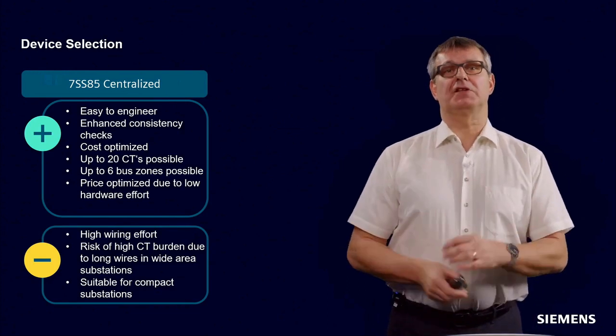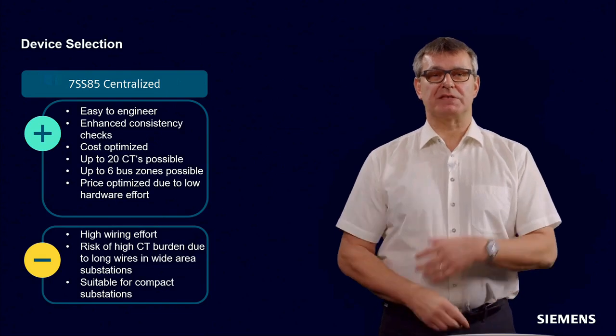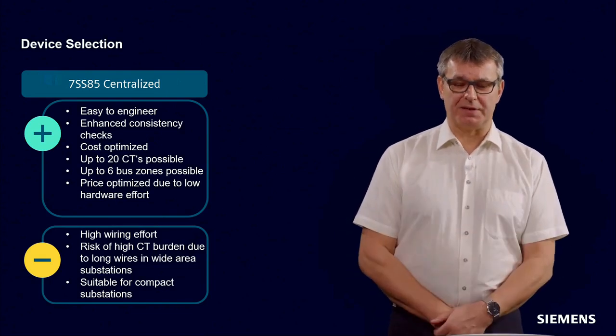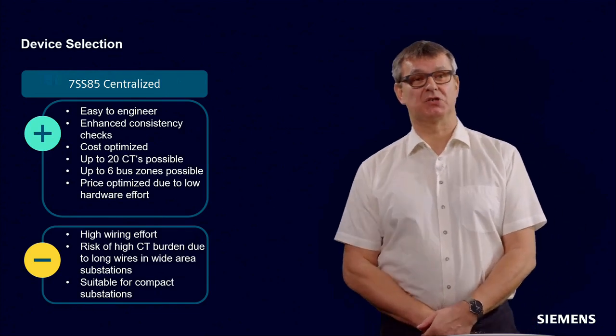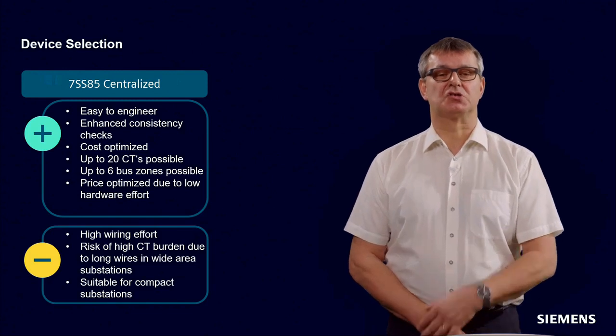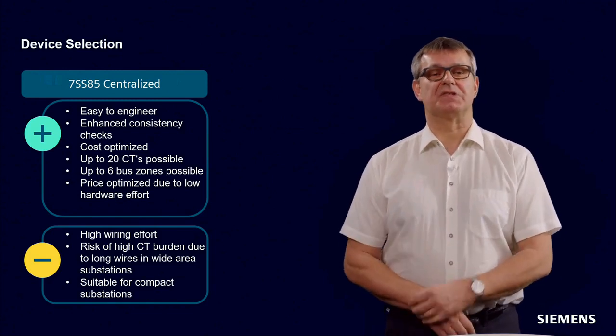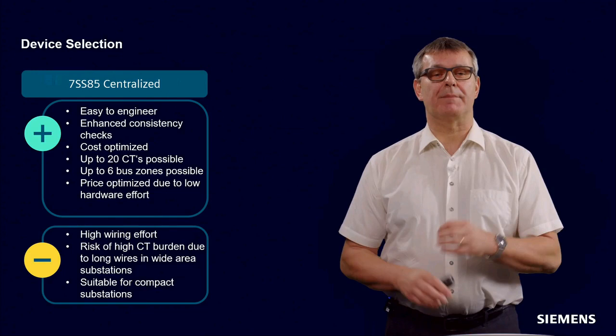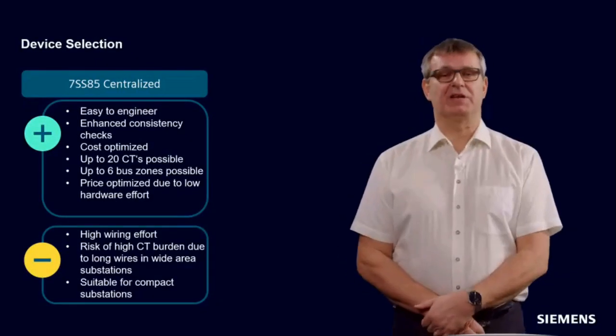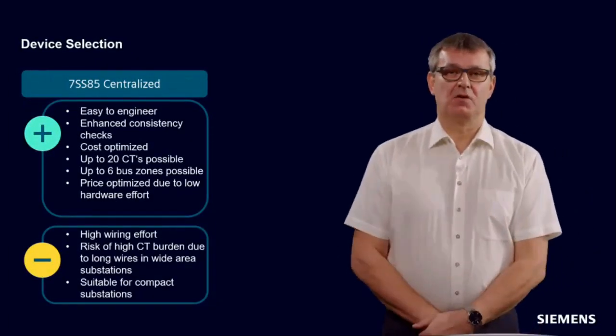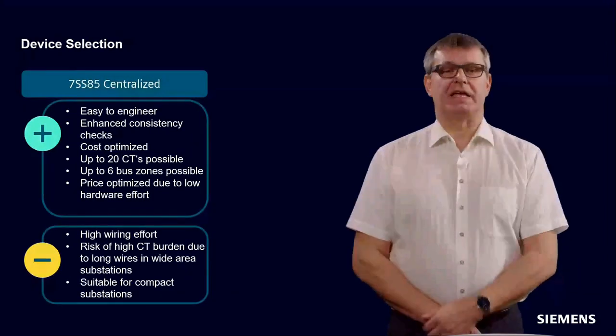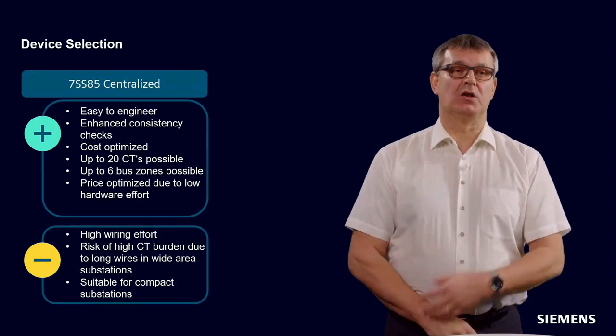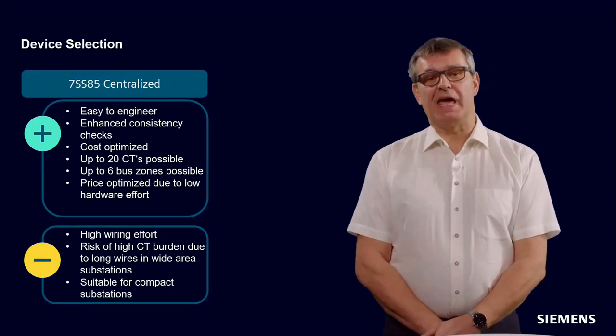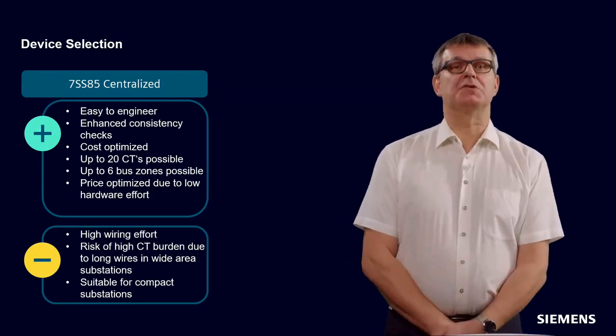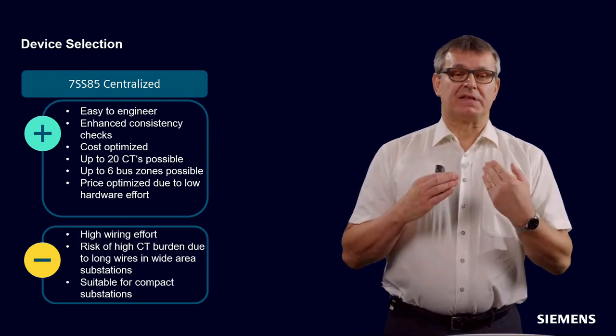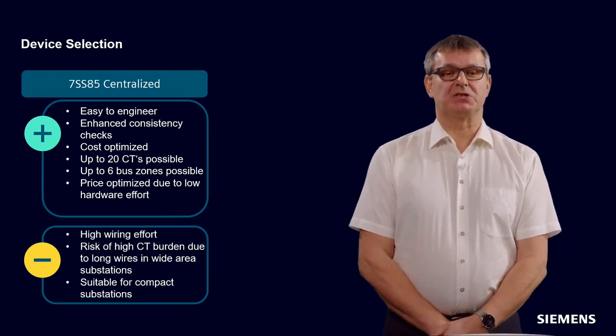This may be a disadvantage compared to the distributed busbar protection, but compared to really all other competitors of busbar protection devices, this is really a big advantage because we are really the only vendor which allows a centralized busbar protection with up to 20 CTs, 20 current measuring points, means 80 current inputs within one device. We can deal with up to 6 bus zones, and as already said, it's price optimized due to a low hardware effort. What may be some disadvantages? Now we come a little bit also to the questions I said I will answer during my next part of this presentation.